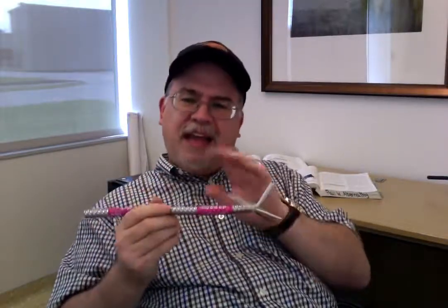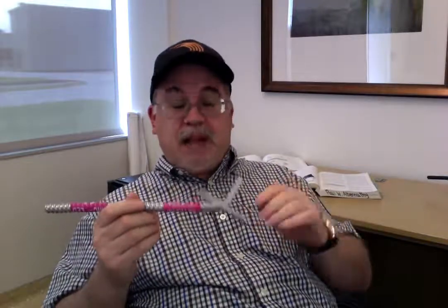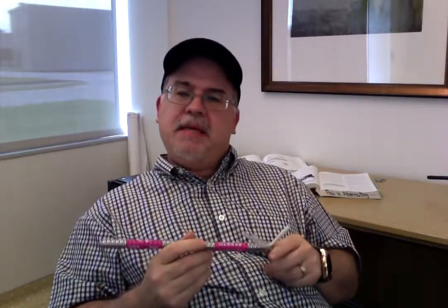So traditionally, you have things like a 2-inch separation that's required when you put the low voltage conductors inside of a raceway with the higher voltage type of conductors. I wouldn't say much high voltage, 120 volts applications like that. You've got to have that separation. Well, this product is meeting an allowance within the National Electrical Code under 725.136 I1 and I2, to be honest with you, probably could meet both.